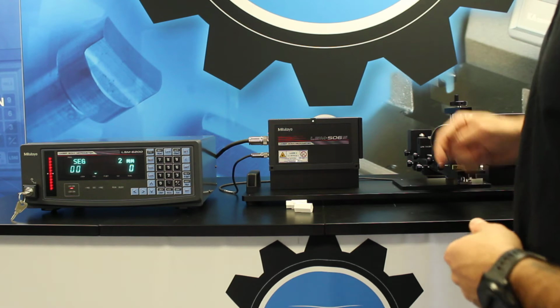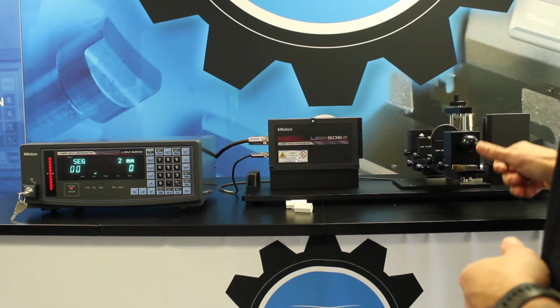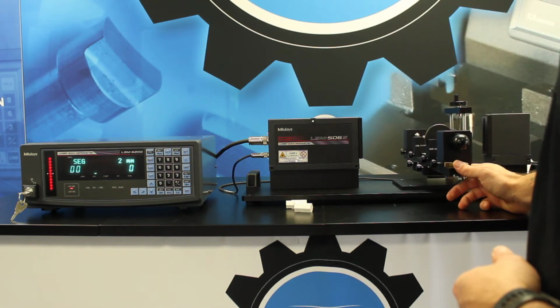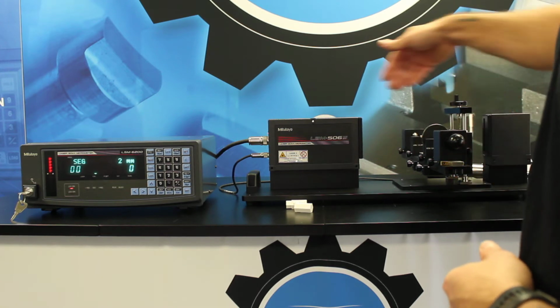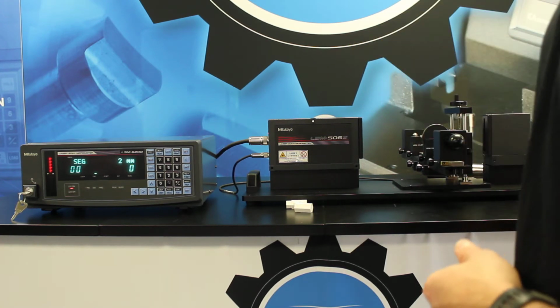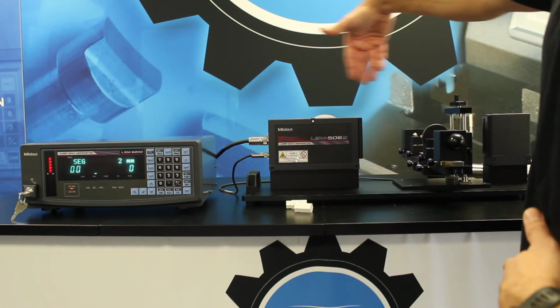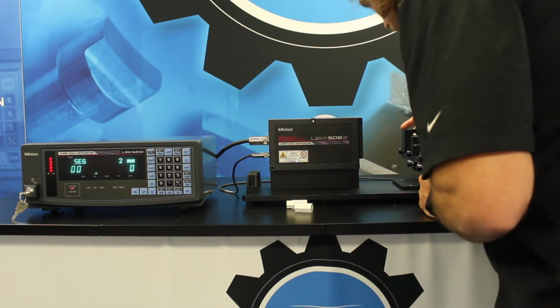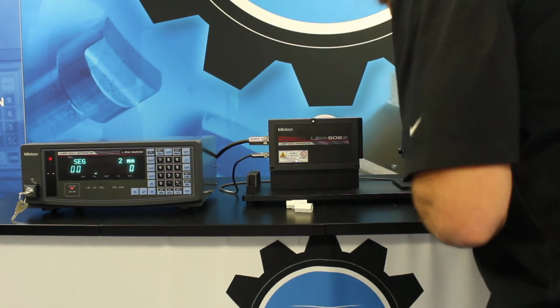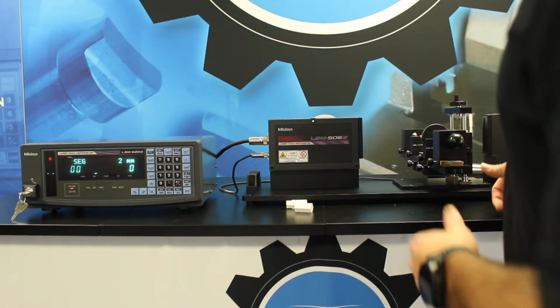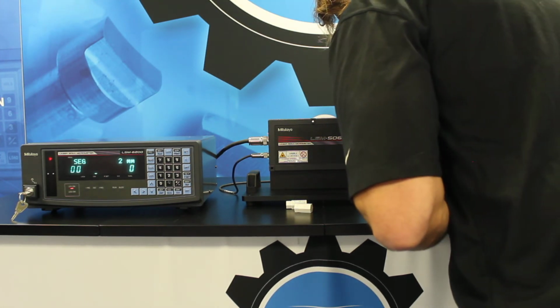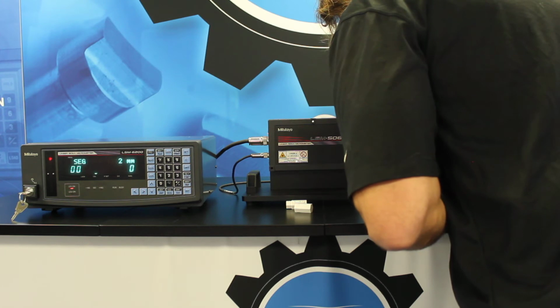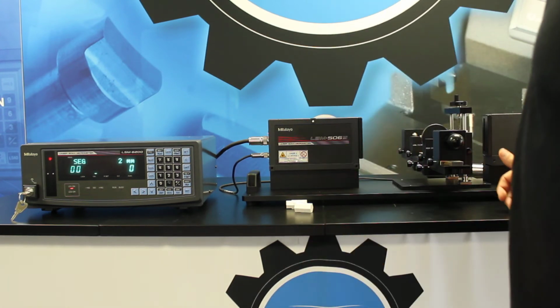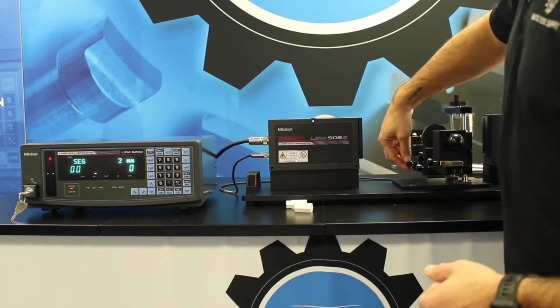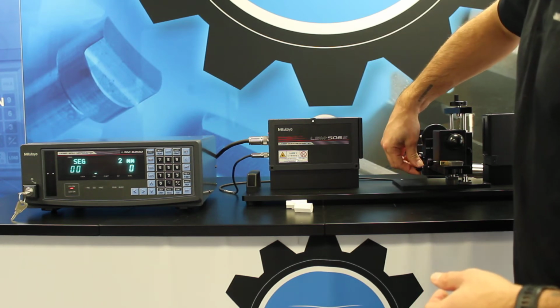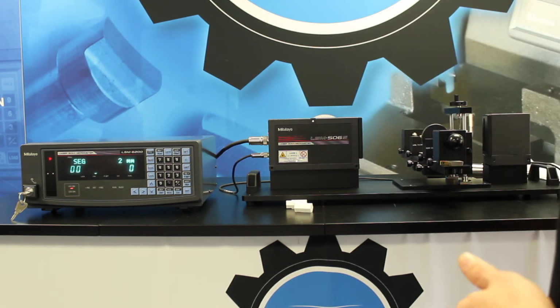And I'm now going to start with the high calibration block first. So I'm going to slide this to make sure I am in front of the sending and receiving unit. I can get a good visual on that by looking over top or from behind the sending unit. I now know I am on that diameter. I'm going to try to get that as centered as possible, and once I've reached that desired location, I'm going to lock that rail in place with the thumb screws.